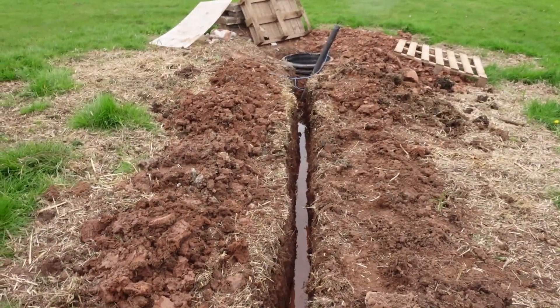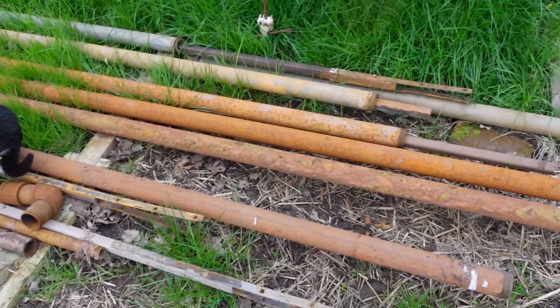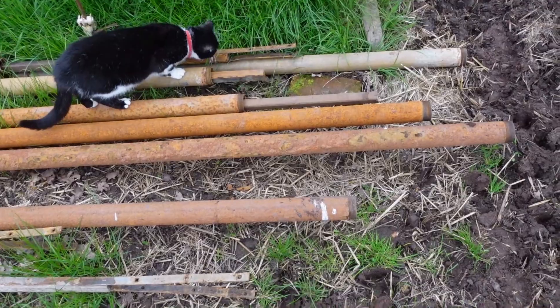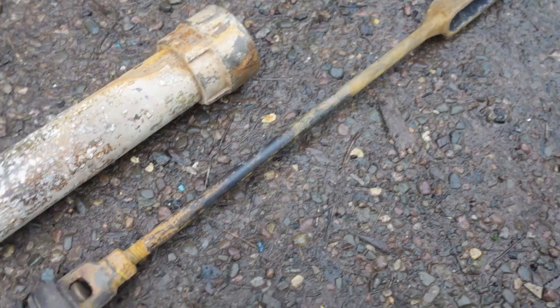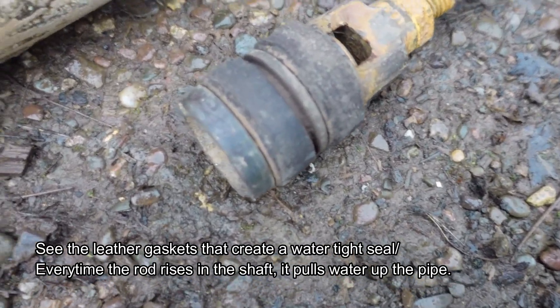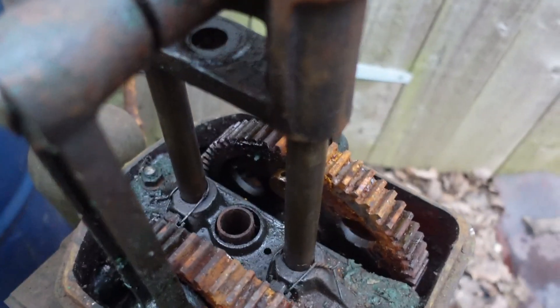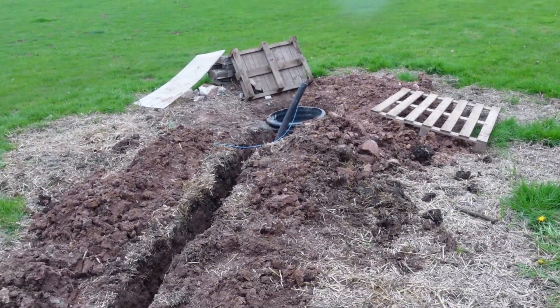It fills up with water just because of where we are, but that's no problem. Just behind me on the ground here is the old borehole pipework, and this is how they used to do it in the old days - you had roughly a two-inch or two-and-a-quarter-inch pipe going right down to the very bottom, and at the top you used to have a pumping mechanism that would oscillate a wooden ram up and down. At the bottom of the borehole you'd have a one-way valve, and at the top you'd have either a windmill or, in our case, a mechanical pump driven by an electric motor or steam engine. That was the old way of doing it; nowadays we have electric pumps that go down the bottom of the borehole to do all the hard work.